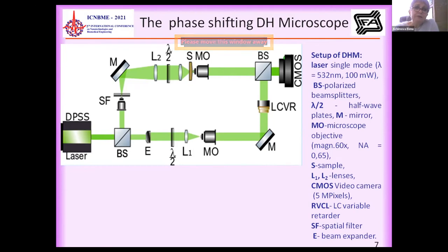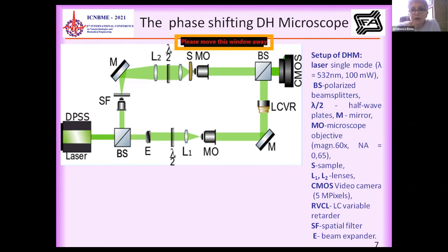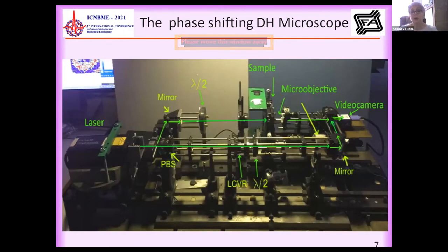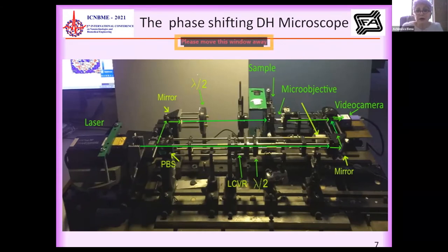This provides high stability of the system, and accuracy of the phase shift applied to the reference beam. All components were mounted on a cage system, which makes our microscope rigid, reduces vibration, and increases the accuracy of the images obtained.